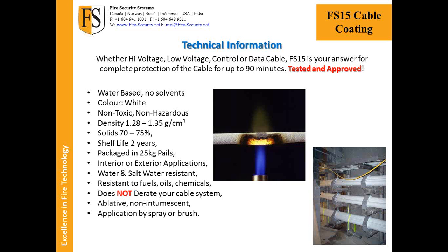Our shelf life is 2 years. We package in 25 kilogram pails or 5 gallon, 18.9 litre pails. It is for interior or exterior applications, and is water and saltwater resistant, which is part of the FM test. There's a saltwater immersion test within the FM test, where they immerse the cable coating on cable into a pail of salt water to see how pliable it becomes, if it's doughy or it comes off the cable. Then they pull it out, let it recure, and ignite it to see if it still carries all of its fire retardant properties, which of course, as we have the approval, it does.